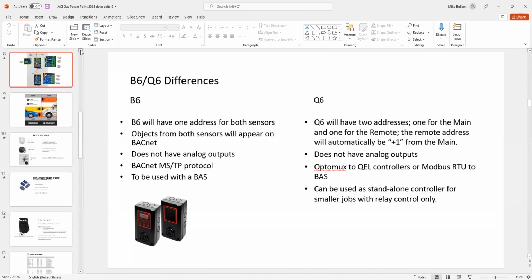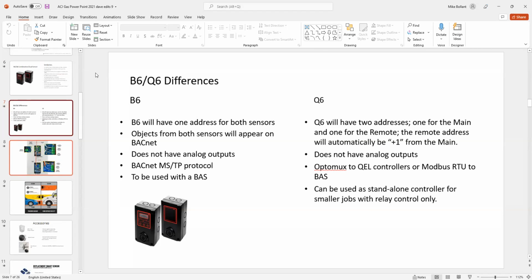We did have one question. How are the MAC addresses set on the BACnet models? On the B6s, they can be set either through the BACnet or at the sensor itself. It would probably be easier to do it at the sensor itself because they all come out with the same MAC address of 4005. So if you have everything powered up and try to discover, it's going to be kind of a mess to determine which one is which. Either way works for the MAC address, and the same goes for the device instance number: it can be done at the sensor or through the BACnet. Cool deal.